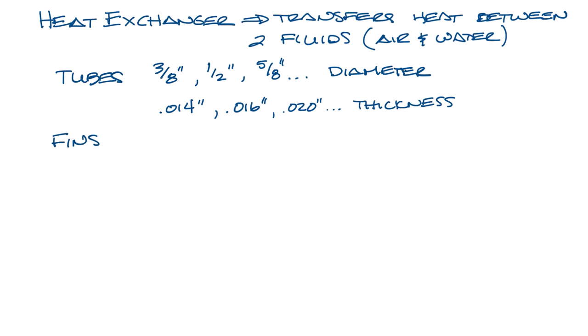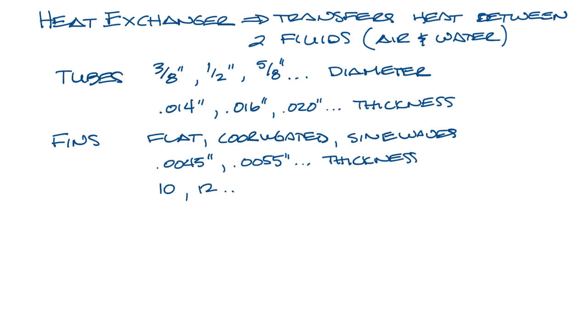The fins can be different styles like flat, corrugated, or sine waves and have different thicknesses like 0.0045 inches, 0.0055, 0.006 inches, and so on. And you can have different fins per inch like 10 fins per inch or 12 fins per inch. The variation in the thickness, diameter, and fins per inch affect the performance and the cost of the coil.